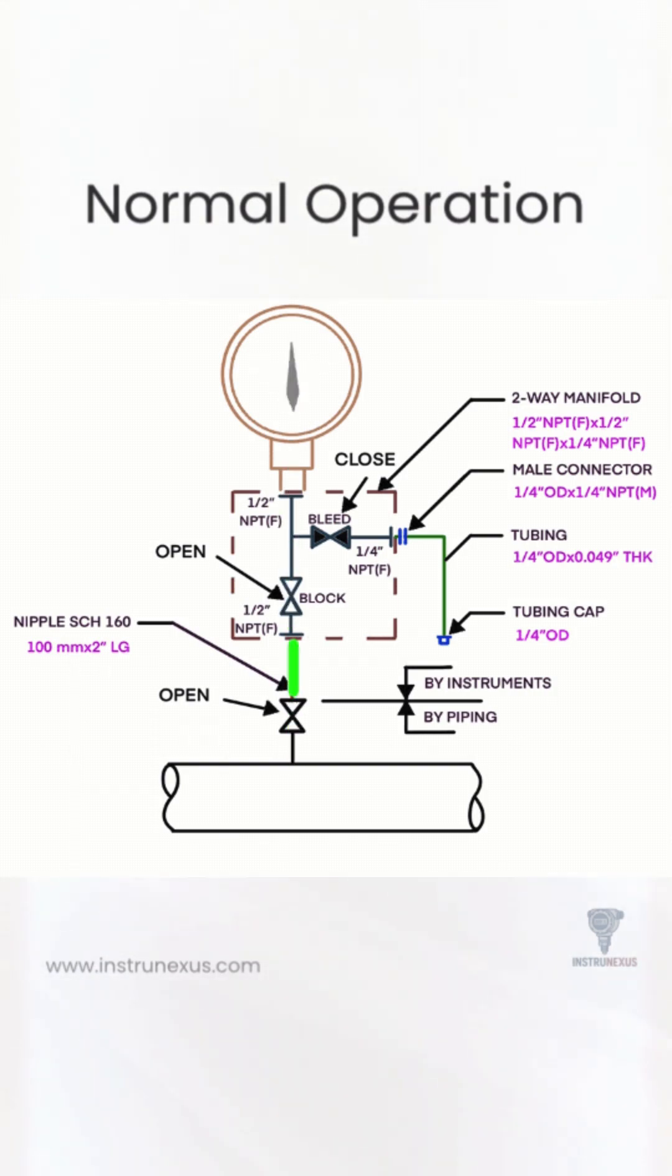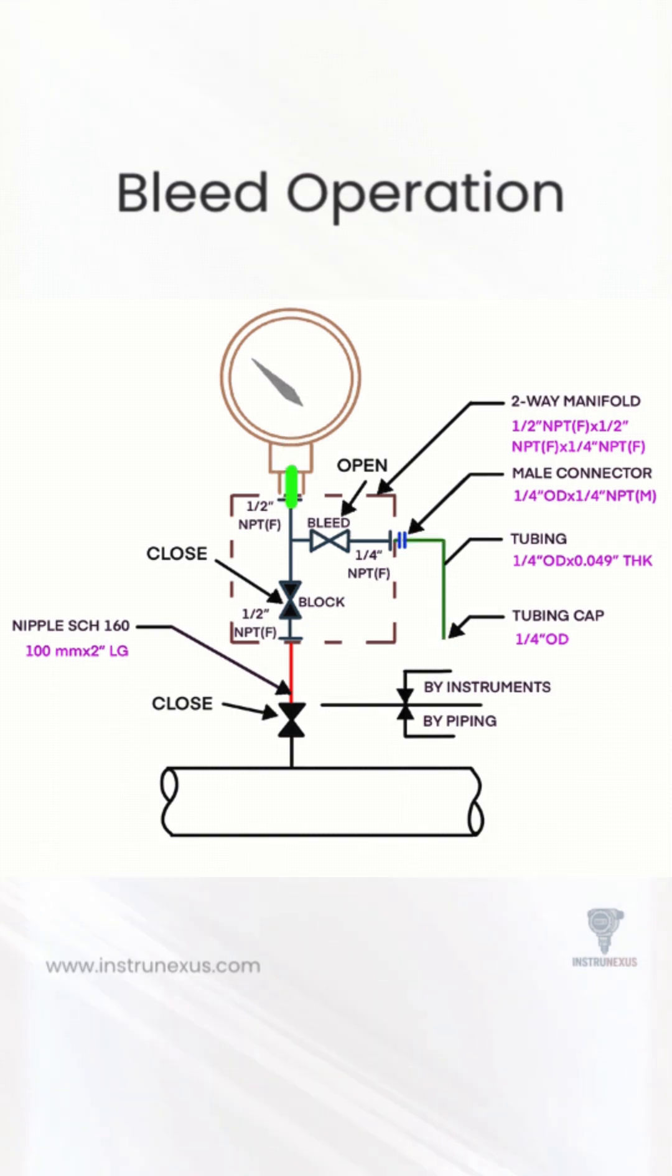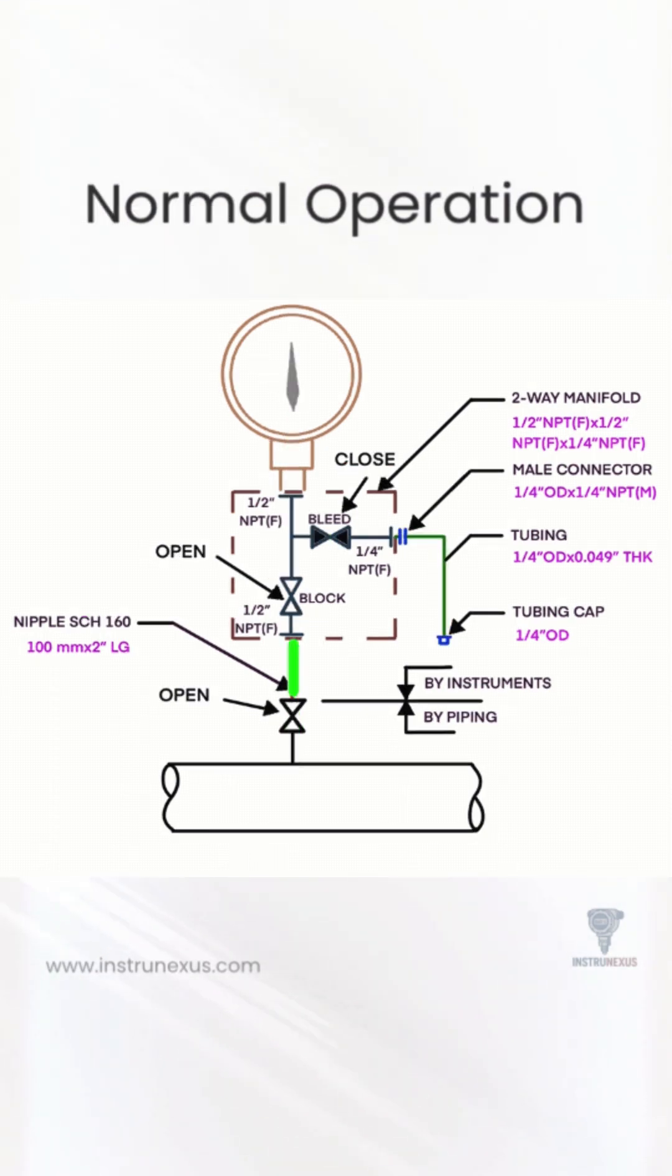The pressure gauge is mounted on top of the manifold with a half-inch NPT female connection, displaying the actual process pressure. For venting or calibration, a one-quarter inch tubing line with a male connector and tubing cap is provided.